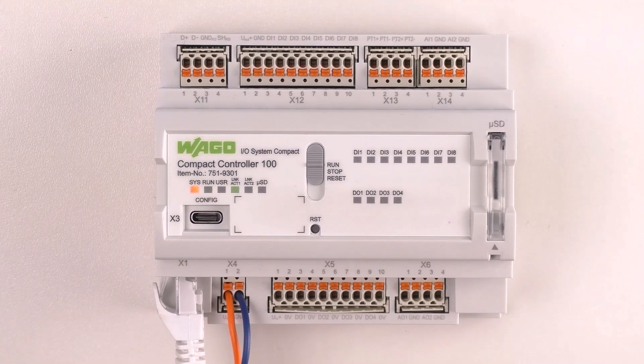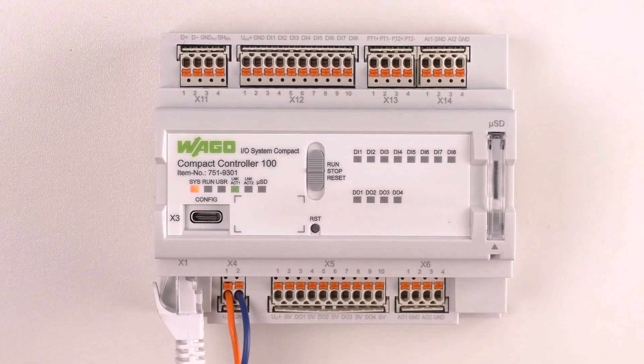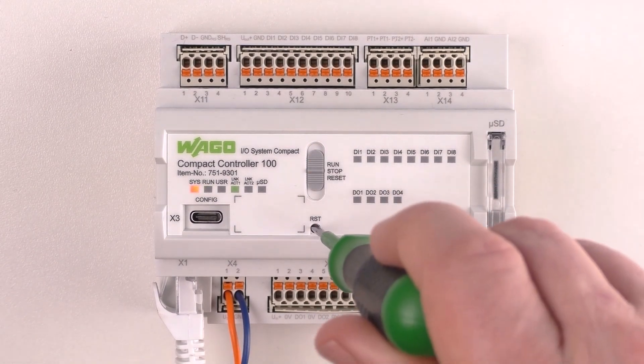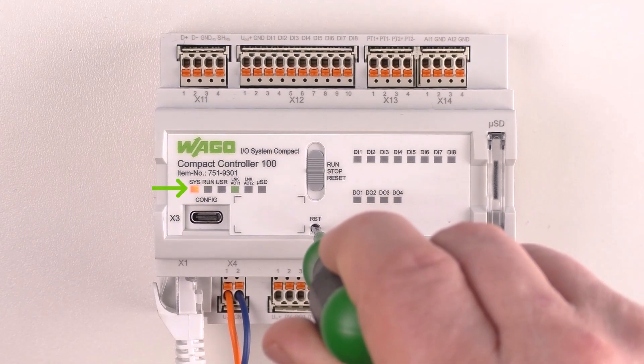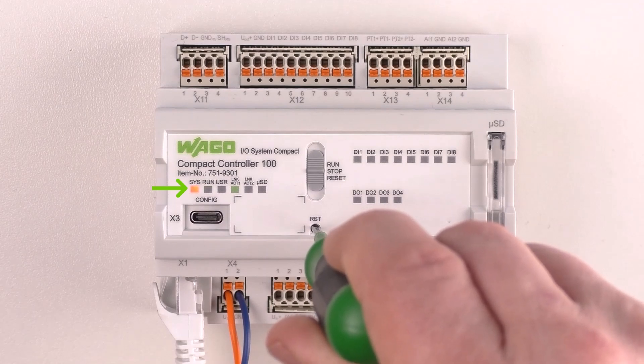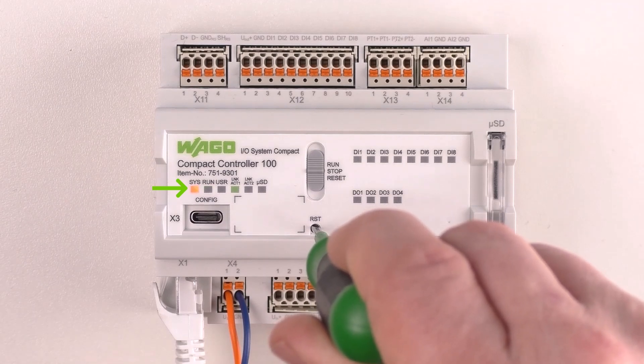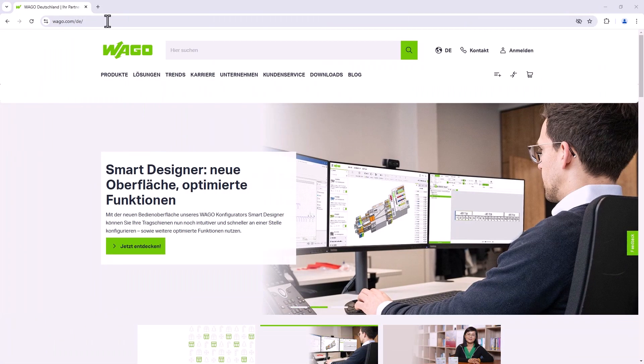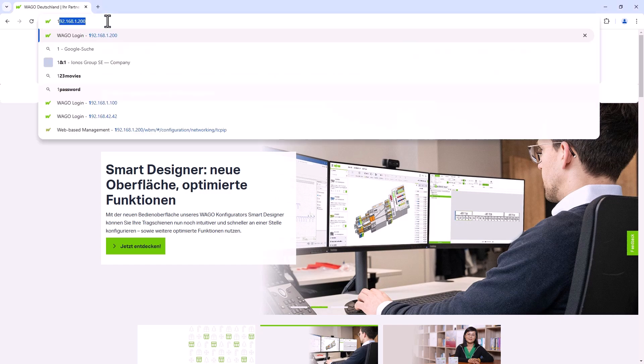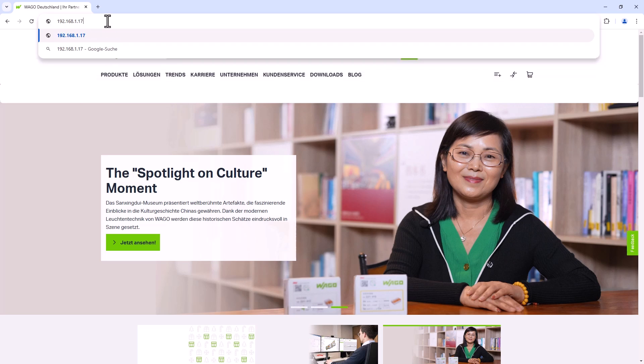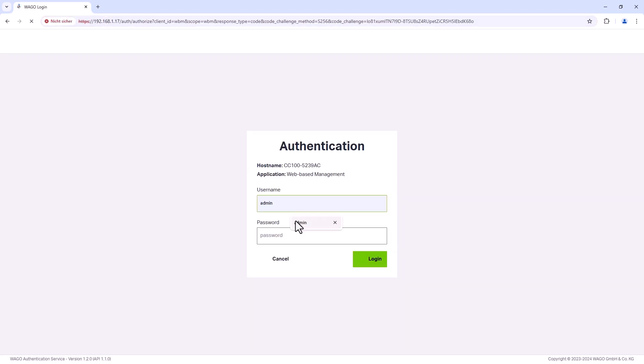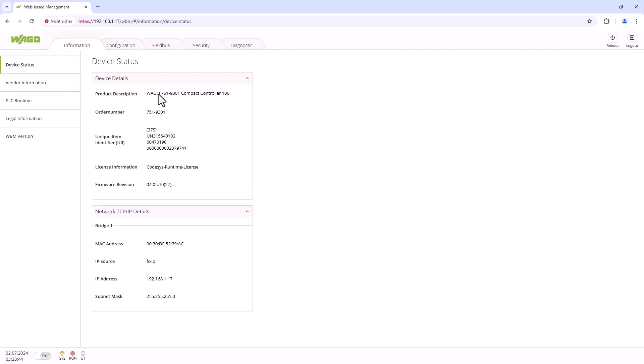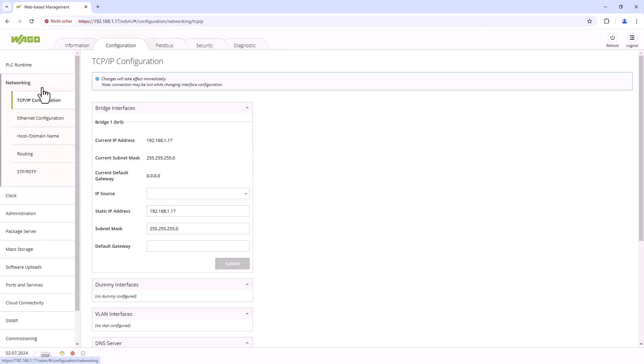Another way to access the controller is to use the reset button to assign a temporary static IP address to the controller: 192.168.1.17. Set the CC100 we have just used to stop and press the small reset button RST for at least 8 seconds until the system LED flashes orange. Now we can access the controller, for example in a web browser, using the IP address 192.168.1.17 and assign it an IP address.